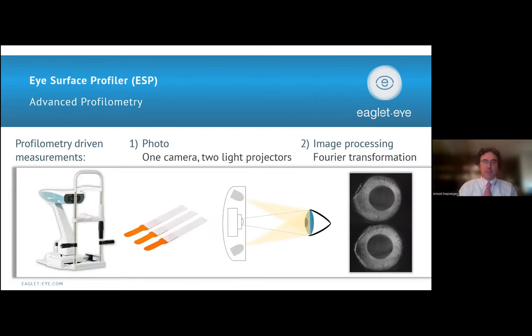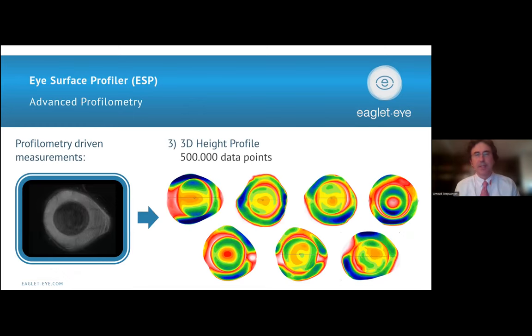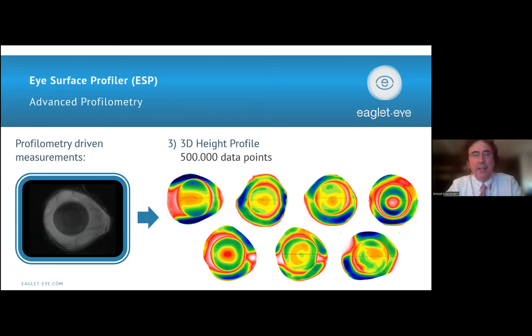The technology is called profilometry. The secret sauce is fluorescein instilled on the tear film. The device projects from two sides a vertical line pattern on the eye in milliseconds, and those photos are processed into 3D height data. You can see a number of maps that come out of a measurement of an eye, letting you see the exact shape of the cornea but also of the sclera.